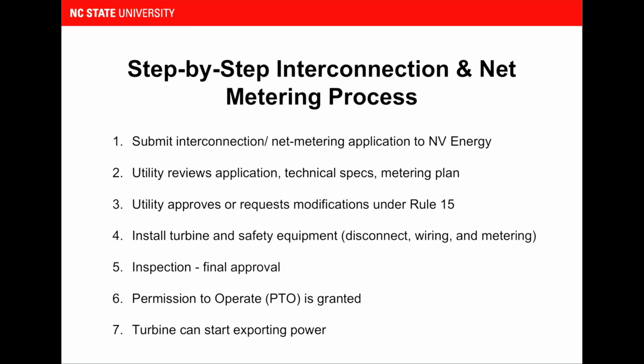The first step is submitting the interconnection and net metering application to NV Energy. This application includes the equipment specifications, electrical diagrams, and metering details. Next, NV Energy performs a technical review. This would include verifying that the system complies with Rule 15, which I mentioned earlier, and that it also meets safety standards and won't negatively impact the local distribution grid. After the review, the utility will either approve it or request modifications, usually related to metering, protection equipment, or wiring clarity.